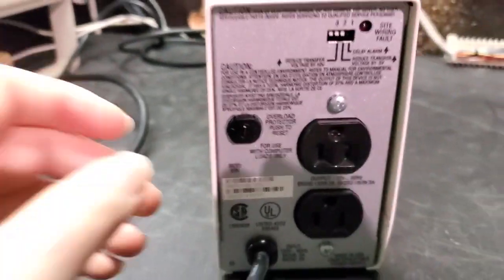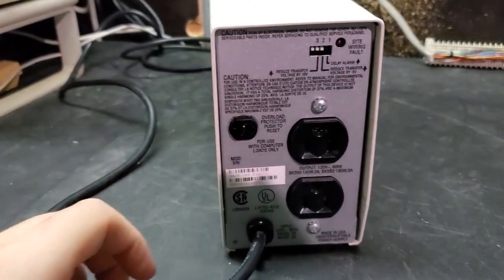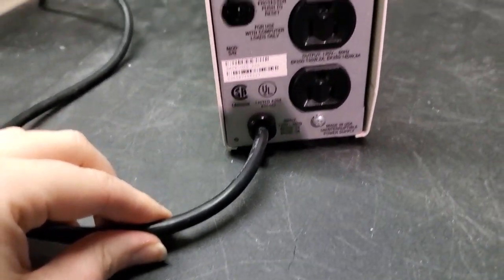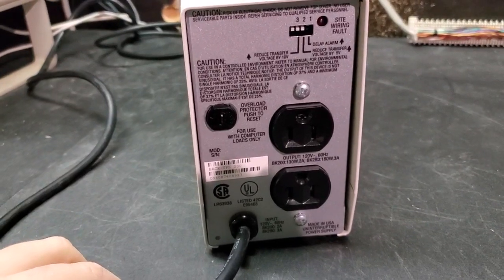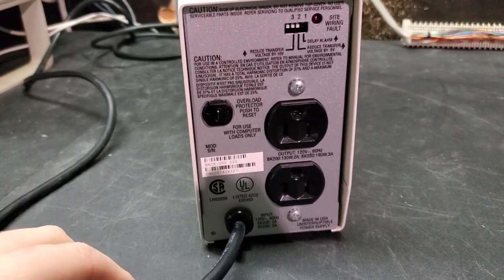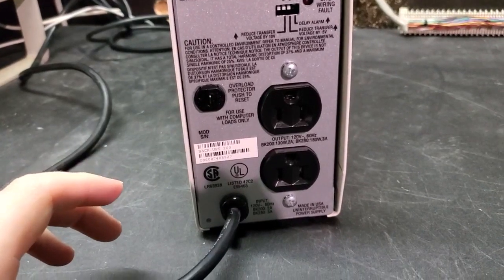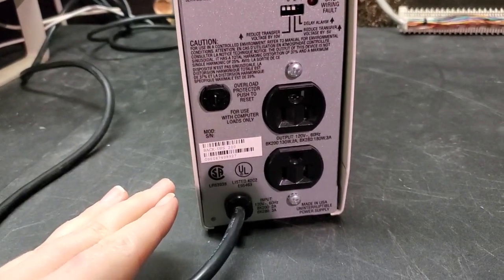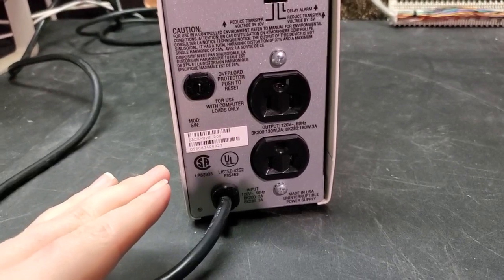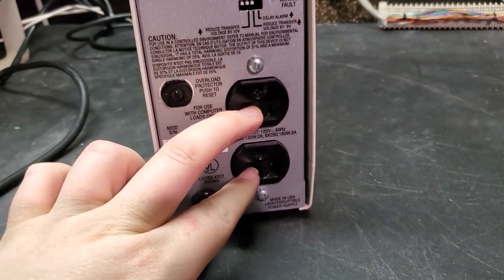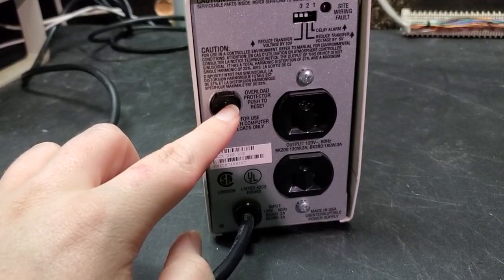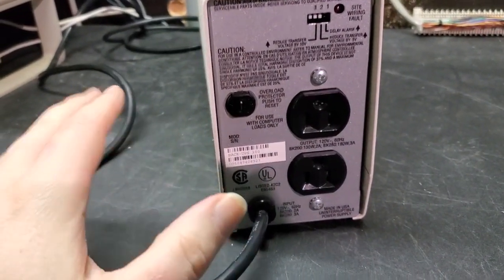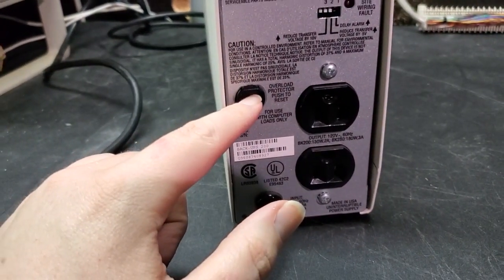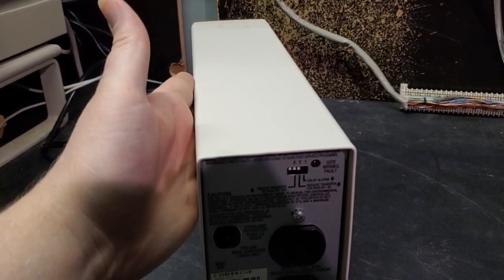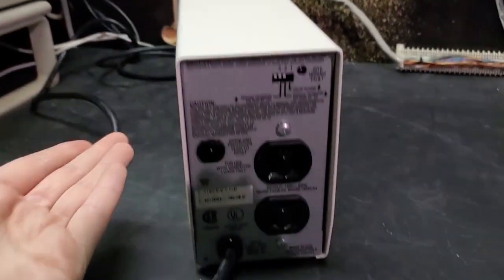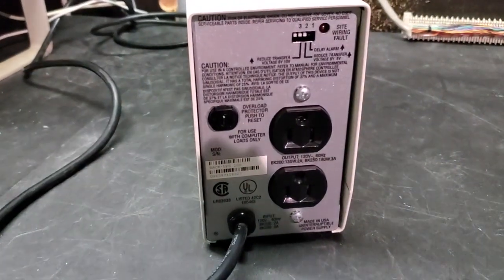We've got a circuit breaker here, pops out on an overload condition. The circuit breaker is actually in series with the mains cord input here, so it will protect from an overload condition as long as the UPS is running on mains power. If it's running on the inverter and then there's an overload condition, this breaker won't do anything. But I can kind of see why they put the breaker on the main side, because then it also protects in case something shorts on the circuitry of the UPS itself. So maybe that's why they did it.